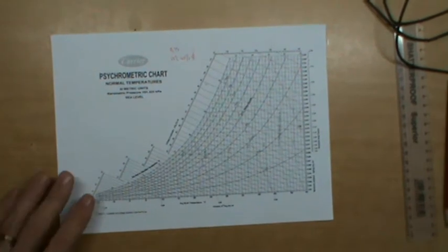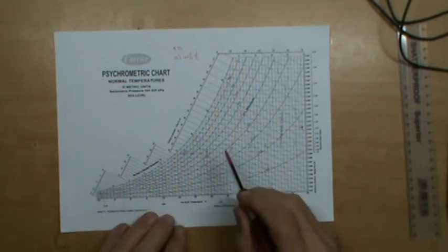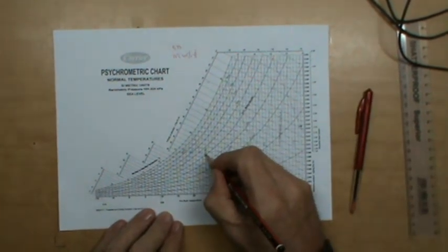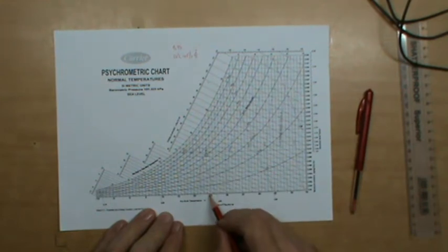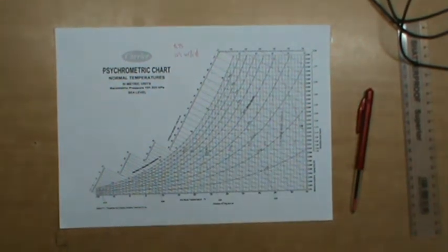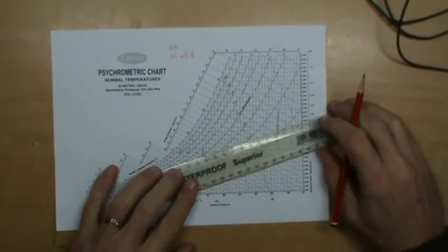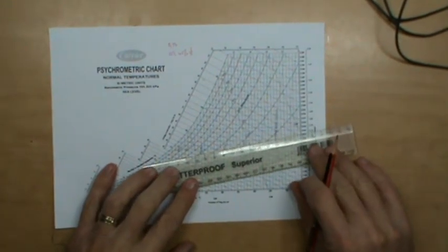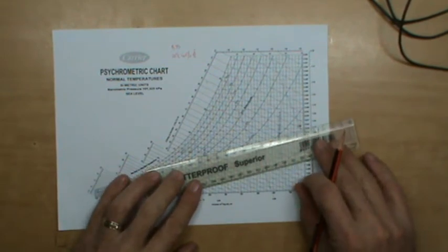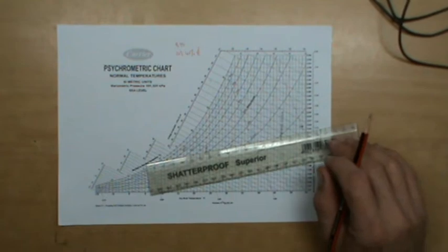Now, remember I spoke about the swivel point or the comfort zone. The comfort zone, I've still got it indicated over here. There I've got it at 24 degrees Celsius dry bulb and 50% relative humidity. And that is a swivel point. That's the point that you line up between there and 0.75 over here on this side. Or if your effective room sensible heat is 0.7, you'll be over there. If it's 0.65, it'll be over there. But that is a point that's the hinge that this whole thing works about.